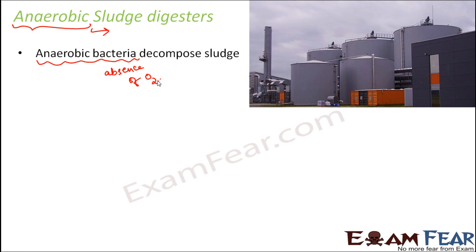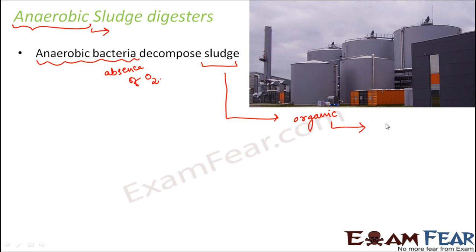Construction-wise, these digesters are closed circular tanks. They are huge and closed. Why are they closed? Because these are anaerobic — they do not want oxygen to enter. Inside, the anaerobic microorganisms break down the organic matter, because sludge is also organic content. During the process of breaking down, several gases are emitted. Some of the prominent gases are methane, carbon dioxide, and also small amounts of hydrogen, nitrogen, and hydrogen sulfide. These are the major gases produced by the action of anaerobic bacteria.